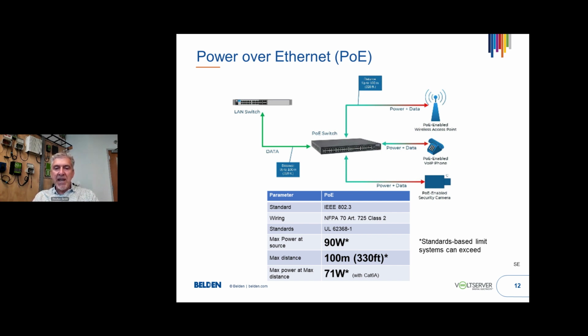It ends up being an endpoint device, where a fault managed power system will often power an entire PoE switch in a zone, and the PoE switch manages all the smaller loads. To date, it's expensive to produce a fault managed power system that only delivers, say, 10 or 20 watts, like what a Wi-Fi access point might draw. So it makes more sense to deliver a lot of power with the FMP system to a PoE switch at maybe 1,000 watts, and then the PoE device distributes it.